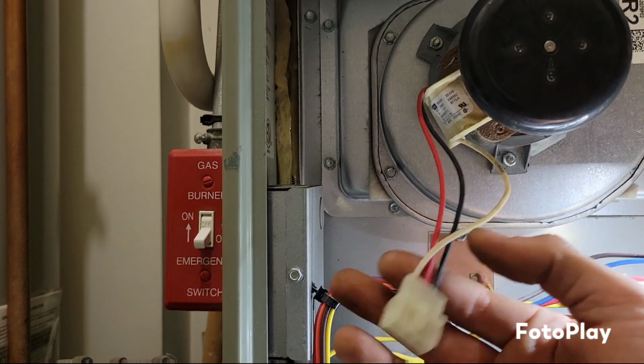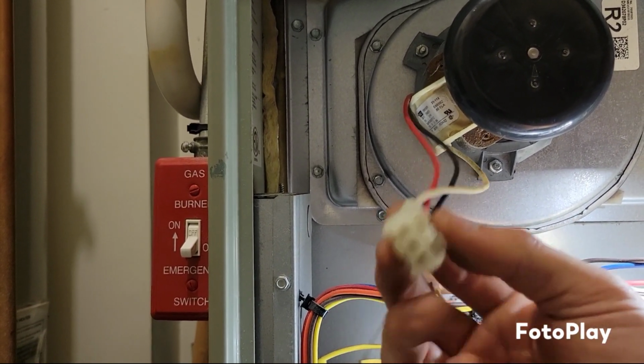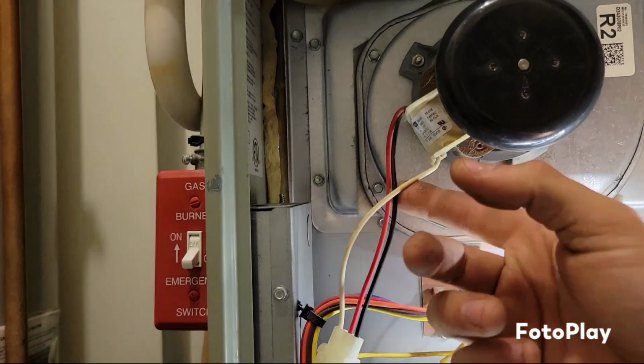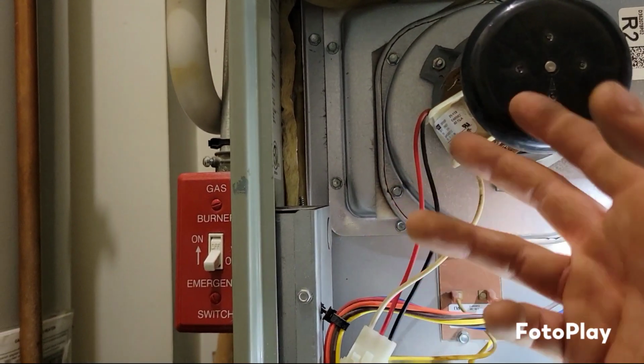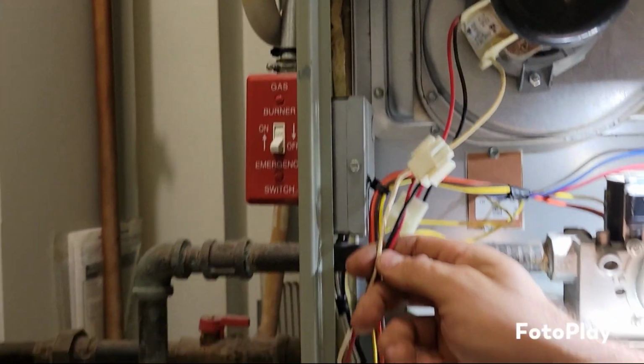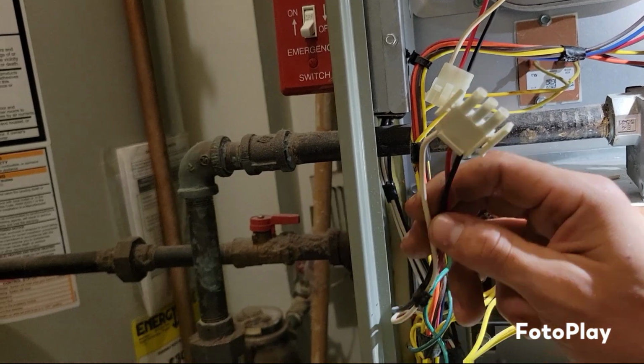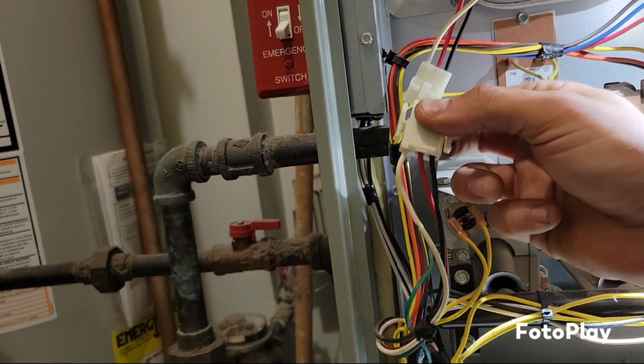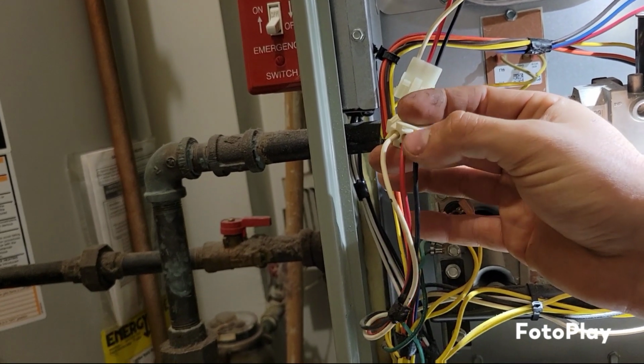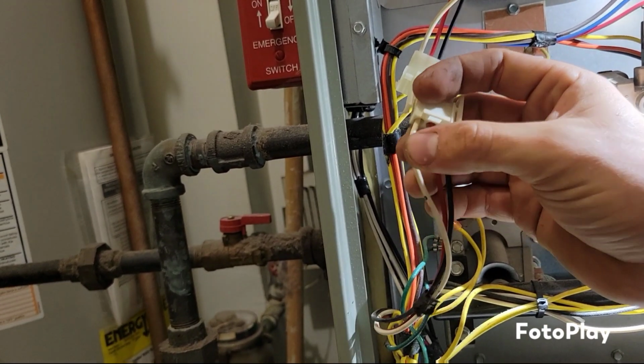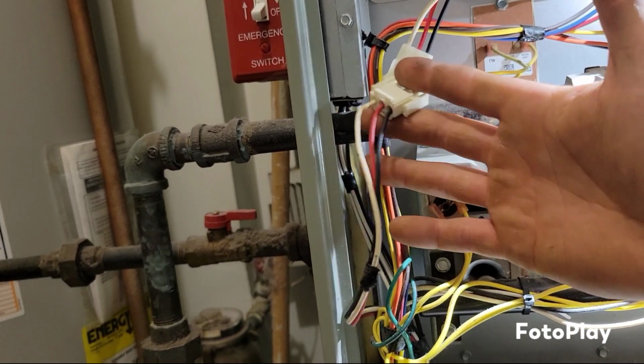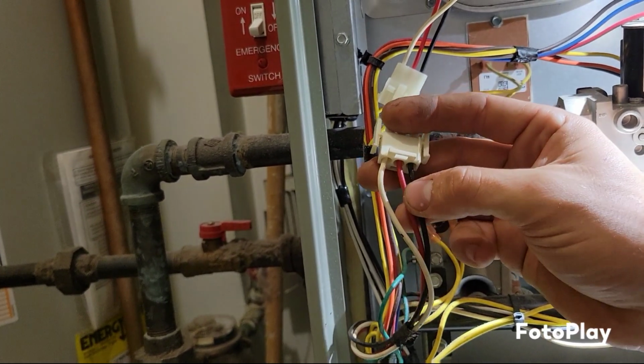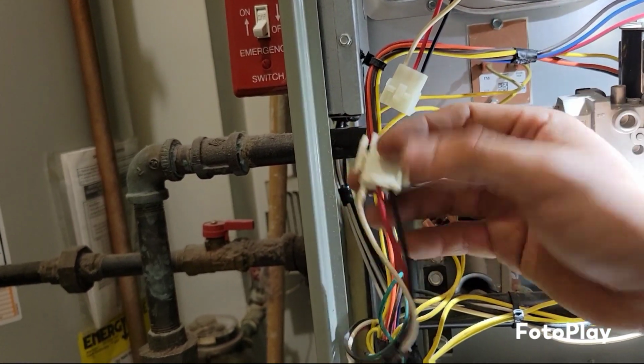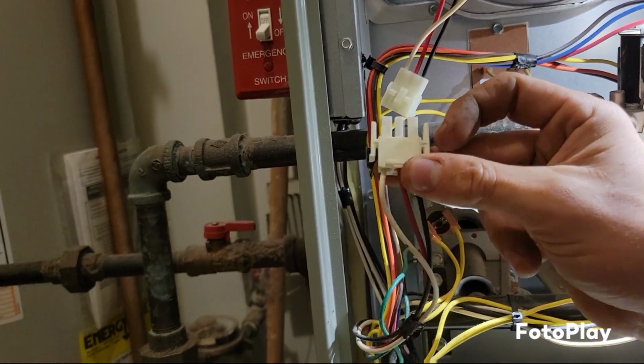Now, the next thing I'm going to check, obviously, I did an ohms test on the motor just to check resistance along the windings and everything, and everything's checking out fine with this. However, when we check power on the bottom side here, during a call for heat, the first thing you're going to get is 120 volts on this particular thing, or a lower voltage depending on the stage of heat that we're calling for. So we check neutral to each leg, and we have nothing. We have maybe 0.7 volts. So we start with 0, and we go to 0.7 volts during the call for heat. That tells me right there that we're having an issue further down in this board.